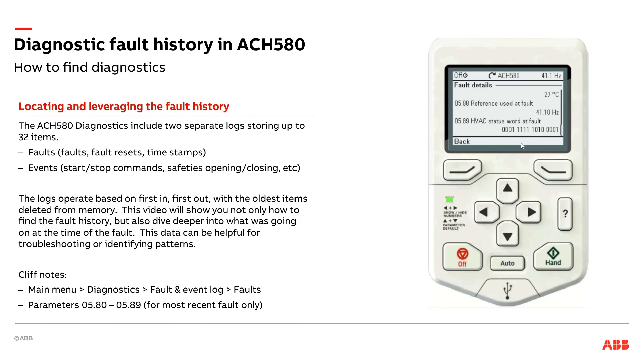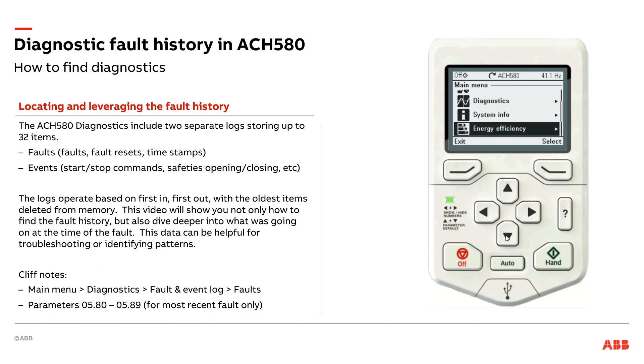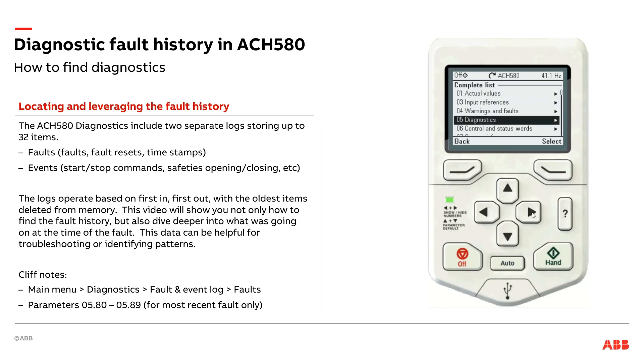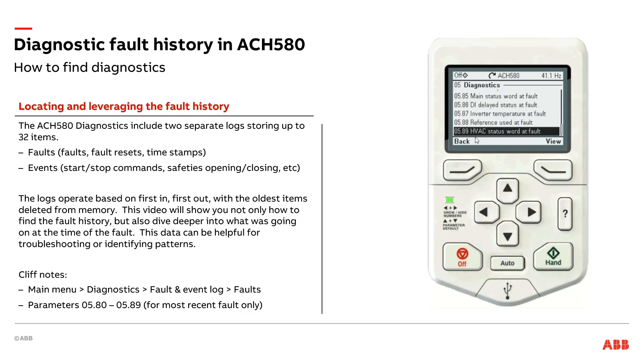But if you're not Neo from the Matrix and you're not able to read all the ones and zeros, don't worry — that's not our intent or expectation. The diagnostic screen is intended to give you that real quick overview of all this information, really easy to read and navigate to. If you need that extra level of detail, I simply back out to the parameters. You could go straight to parameters, but I like going to diagnostics first because it has everything in an easy list. So I go to Parameters > Complete List > Group 5, Diagnostics, and navigate down to parameter 0589. A quick tip: just hit the up arrow and it'll take you to the bottom of the list, right to that HVAC status word.